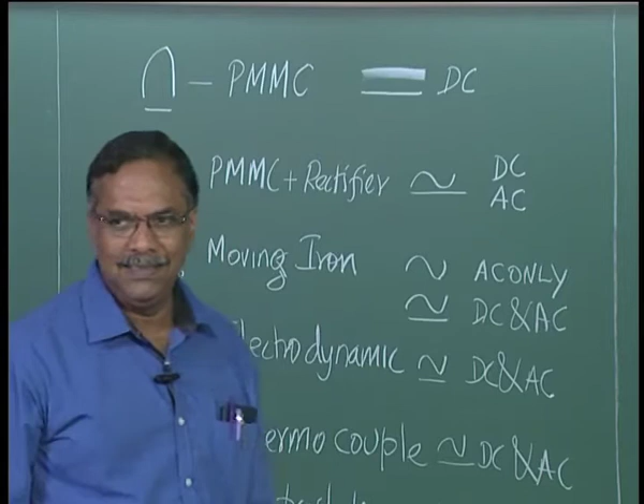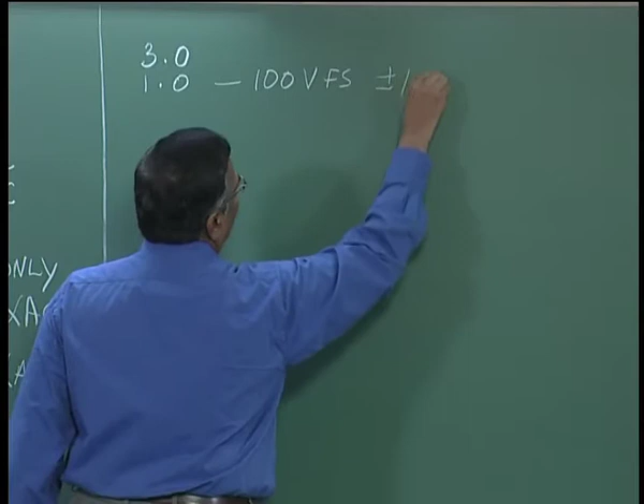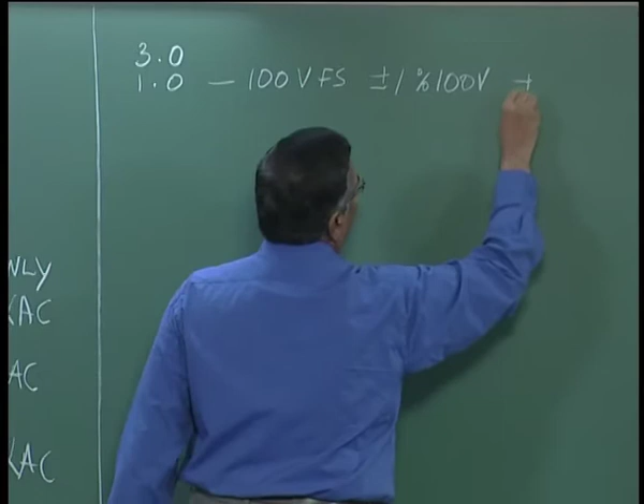For example, if I have 1.0 written and it is a 100 volt meter, full scale, then the error is plus or minus 1% of 100 volts, which is equal to plus or minus 1 volt. So the manufacturer now guarantees that if you use his 100 volt meter, your reading will never be more than plus or minus 1 volt of the expected value. If you are reading, let us say, 50 volts, he guarantees it will be between 49 and 51.